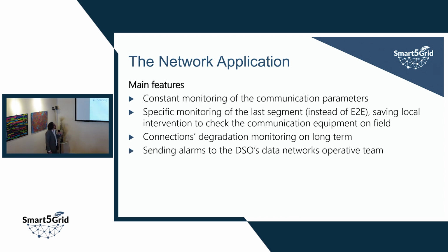So what are the features of this network application? As I mentioned, we are able to monitor constantly the communication parameters. We are monitoring specifically the last segment, saving some effort in avoiding intervention of physical people on field. We can check the degradation of the medium, because for example in the past the parameters were slowly going through a degradation phase, and we can identify that slow degradation and make the correction before it's too late. The network application is also able to send alarms to the technical team to start checking what's going on.